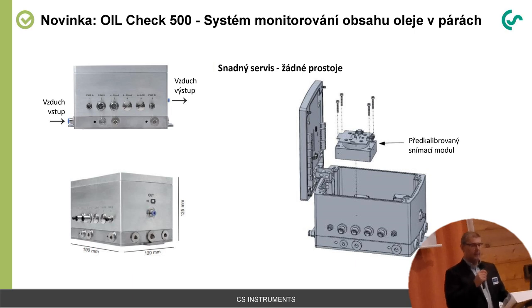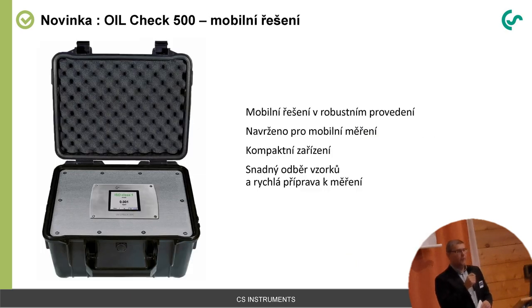Okay, and the nice thing is the so-called pre-calibrated sensor unit. The pre-calibrated sensor unit could be changed on site by the user. All competitors' instruments have to be sent back for recalibration. Ours could be changed on site, so the user can take out the old sensor, insert the new sensor, and go on measuring. And of course, the OilCheck will also be available as a mobile version in a case for all the people who have more than one compressor station.